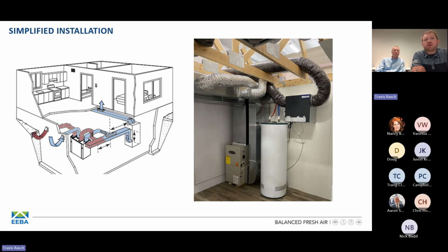This is an example with what we call a return to return. Essentially, we're pulling stale air from the return system, and downstream or close to the air handler, we're introducing fresh filtered air from the HRV or ERV into that ductwork. There's an alternative where you would introduce that fresh air from the HRV or ERV into the supply side of the air handling system. Again, this would require some interaction with your air handling system and these units running, just to make sure we're getting the benefit of leveraging that ductwork and having that air distributed accordingly throughout the house.